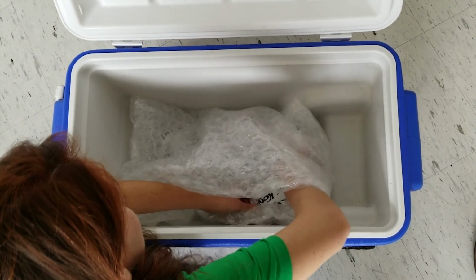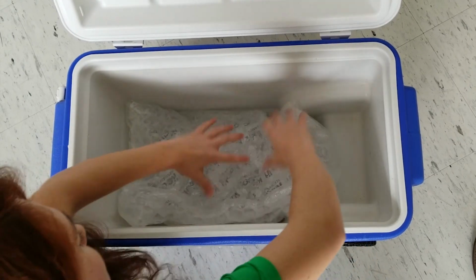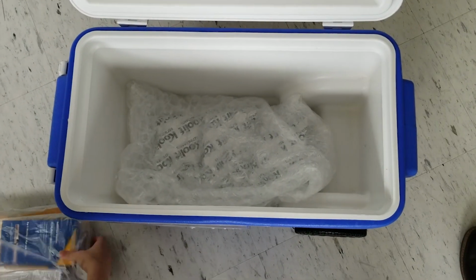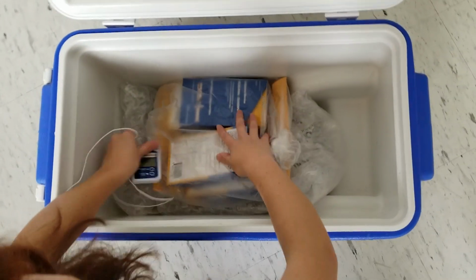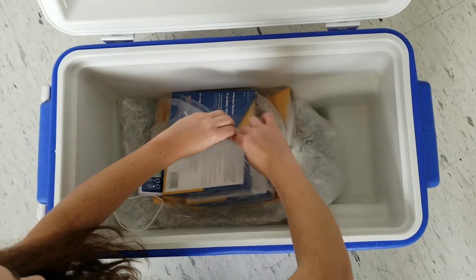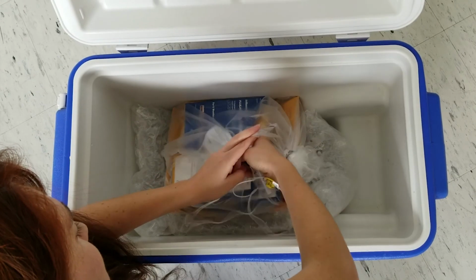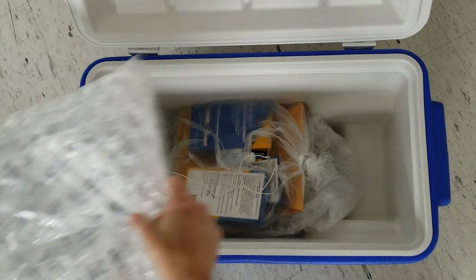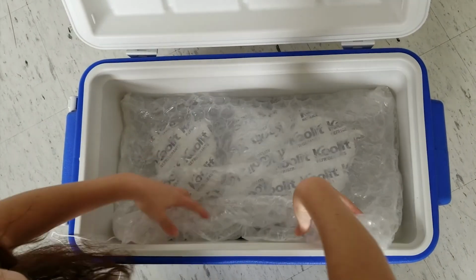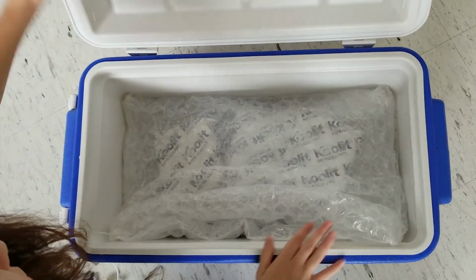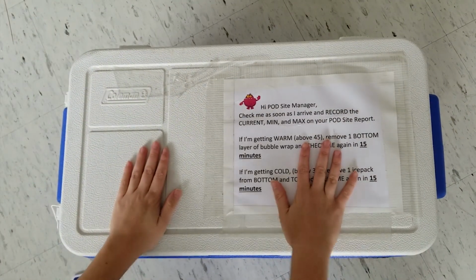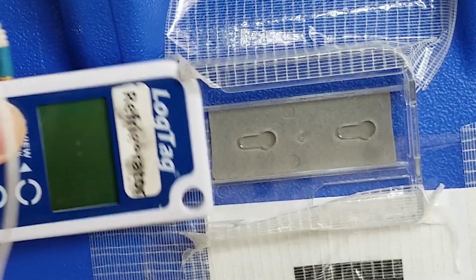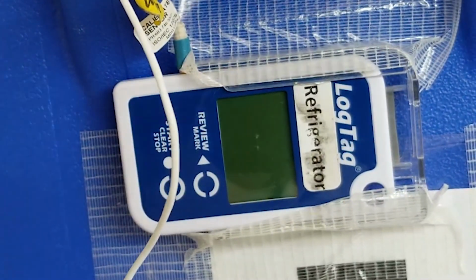Start packing the cooler by placing one of the bubble wrap sleeves containing 3 ice packs into the bottom of the cooler. Next, place the bag containing the vaccines on top of the ice. Here we see our nurse Crystal placing the temperature probe into the center of the vaccine boxes. Place the second bubble wrap sleeve containing 3 more ice packs on top of the bag of vaccines, and close the lid. Place the data logger into the side holder.